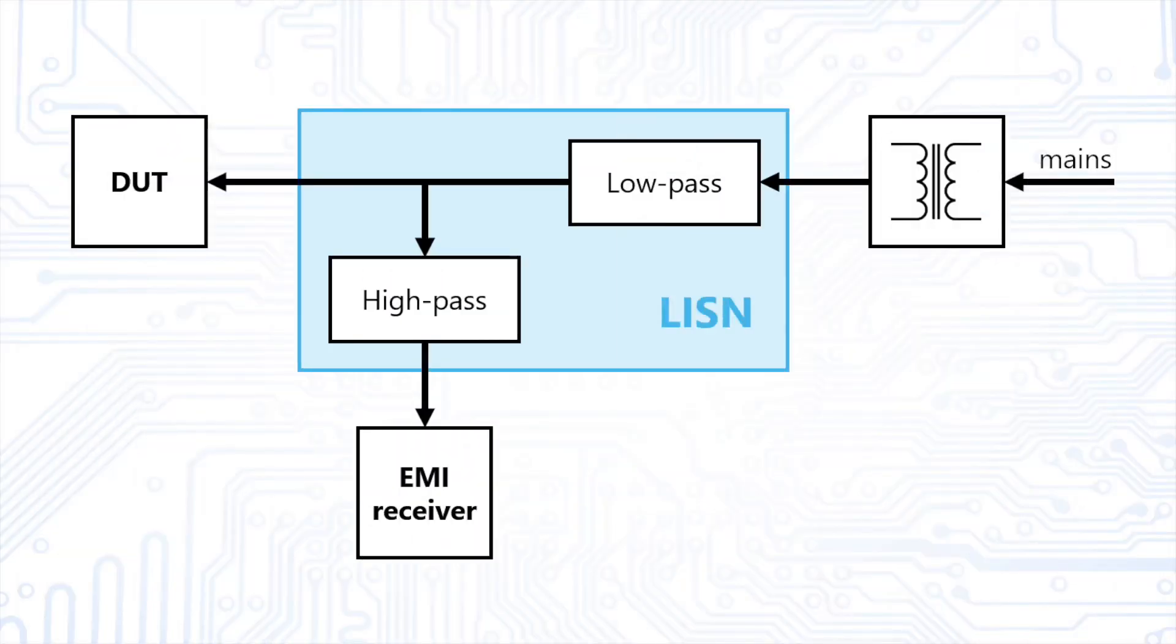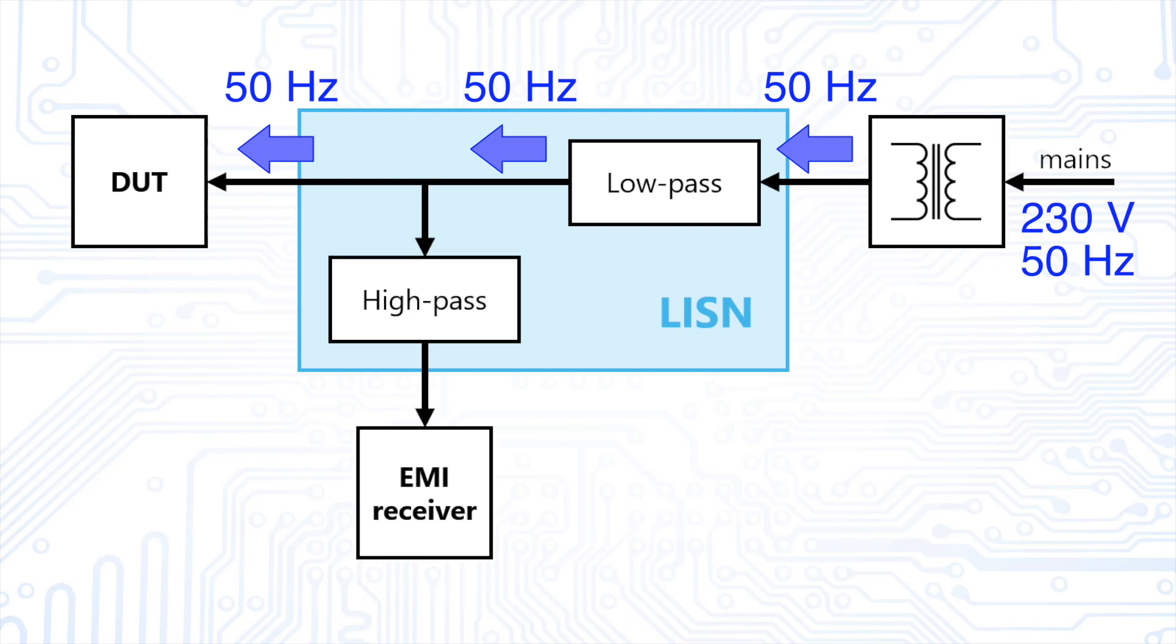This block diagram describes the measurement setup. The 230 volts from the transformer pass through the low-pass filter of the LISN and reaches the DUT. The DUT itself now causes conducted emissions, which are decoupled via the high-pass filter of the LISN. These emissions are then measured with an EMI receiver.